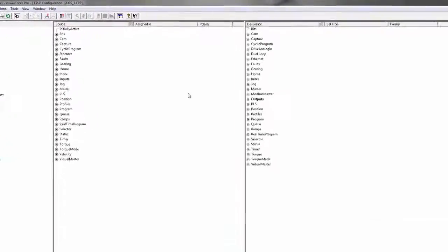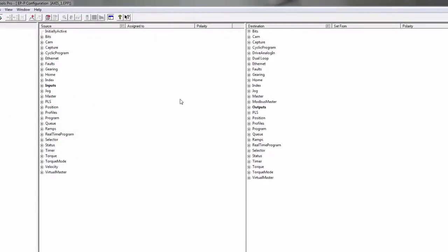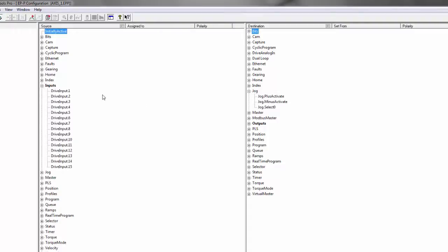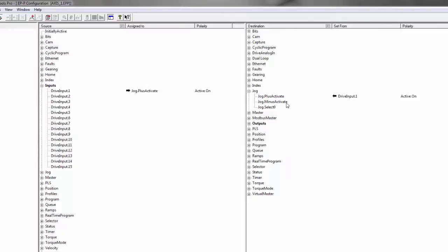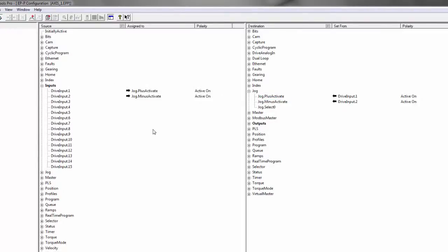Next thing I want to do is my IO setup. Here's where I can assign the inputs that are wired to my drive to how this thing is going to operate. So first thing I want to do is set up my jog. I'm going to simply say I want the first switch to jog at plus, drag and drop that over, and then let's do a minus jog as well.